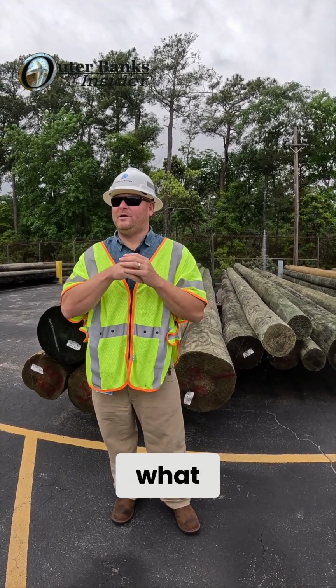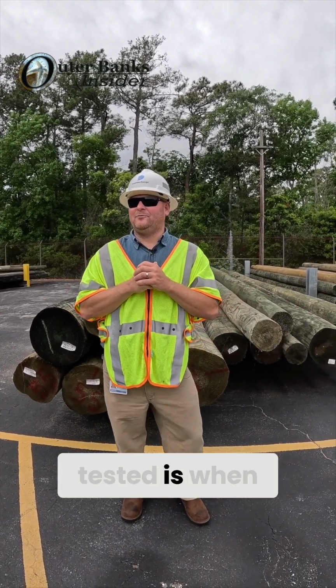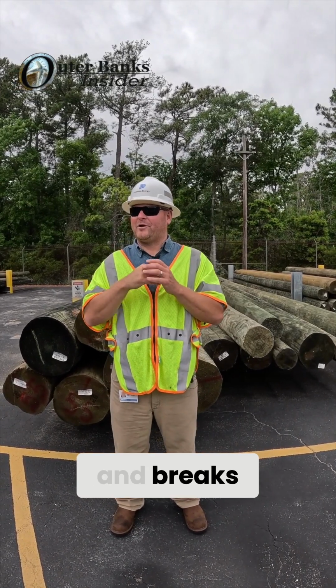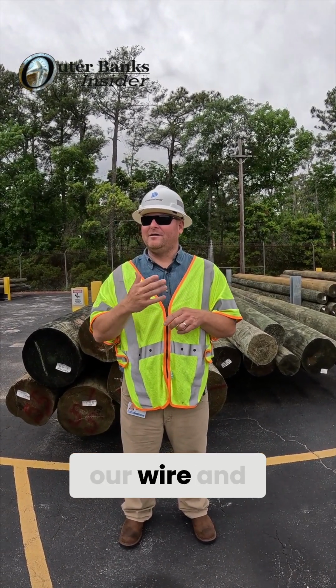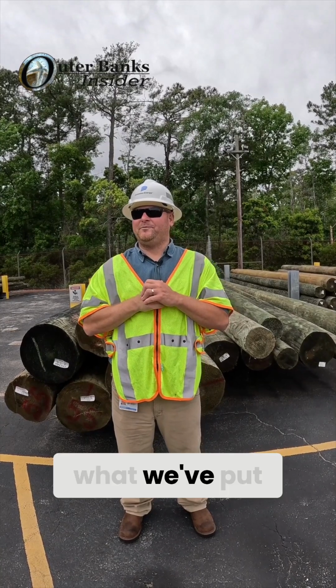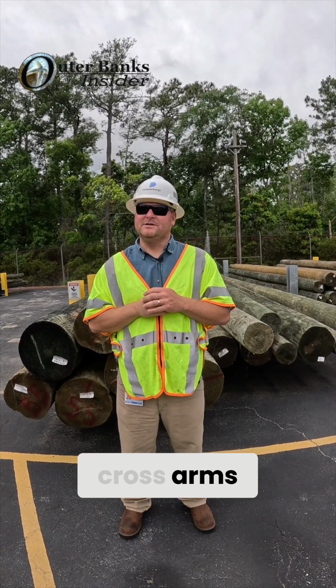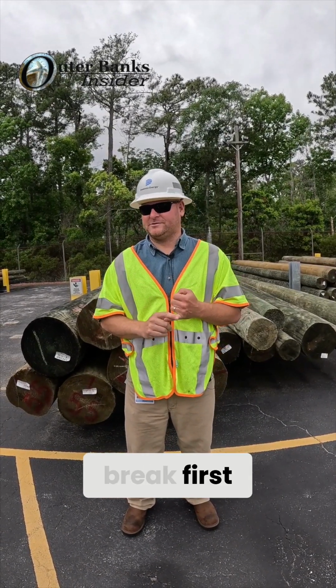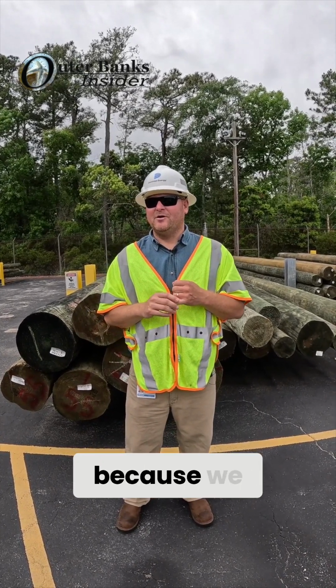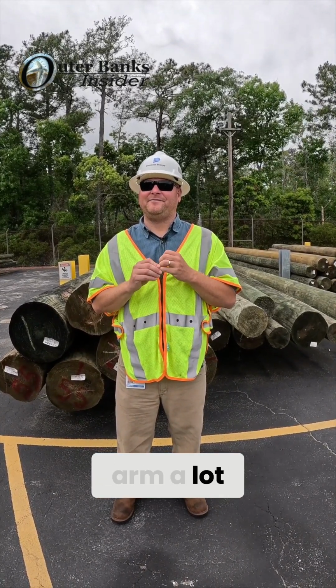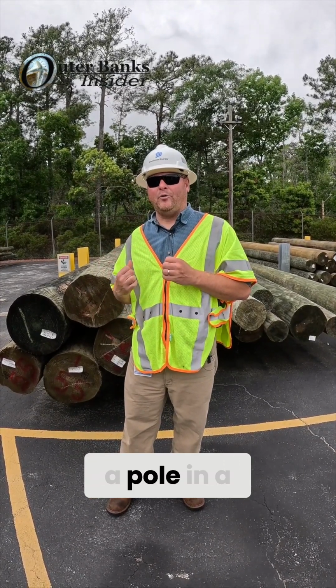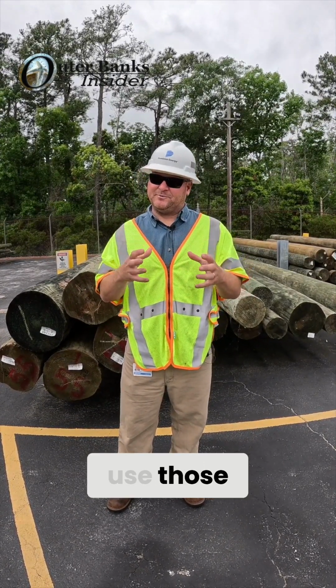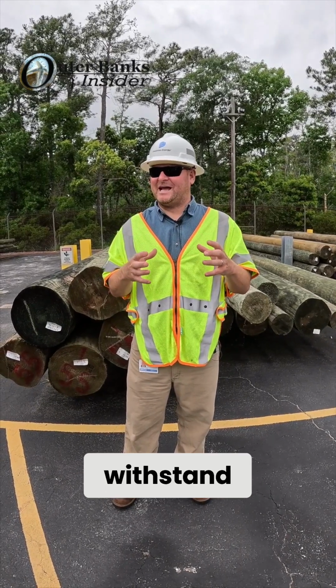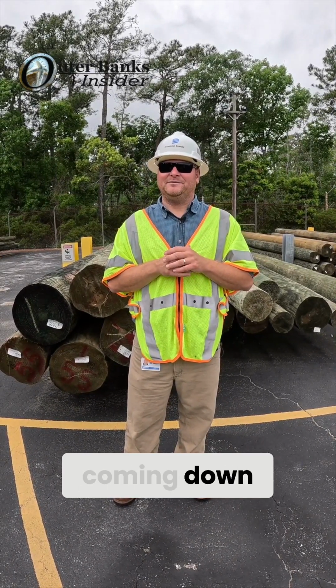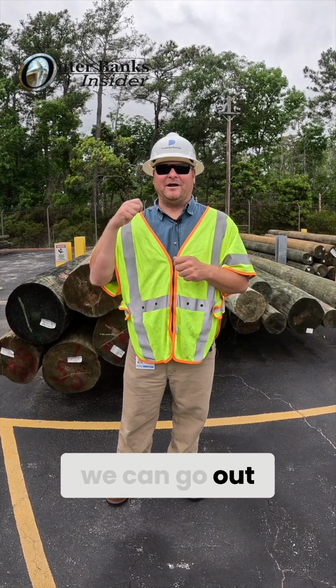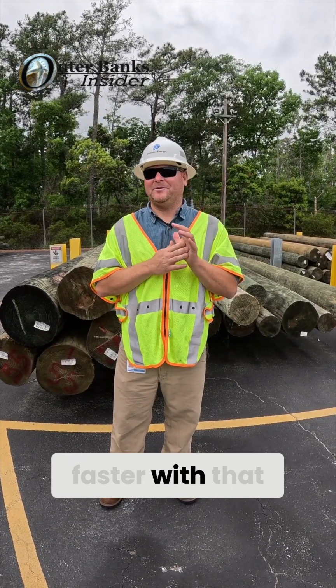What has been tested is when a large tree comes down in mid-span of our wire and tears the wire down. So we've put in place those fiberglass cross arms. We want the cross arms to break first, because we can replace a cross arm a lot faster than we can replace a pole and a cross arm. That's why we use those bigger class poles, so they will withstand a big tree coming down. When we still have a pole standing, we can get the lights on a lot faster with that grid hardening project.